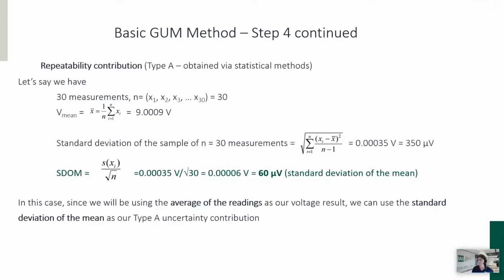There is no set rule really on what's significant and what's not. When I do an uncertainty budget and I see something is tiny, and even if it was a lot larger, it would still not make a dent in the final number, then I would say it is insignificant. However, you have to be careful. Some people say, as a rule of thumb, if it's less than 5% of the total, it's insignificant. But what if you have 10 of these 5%? Then all of a sudden, they can all add up.